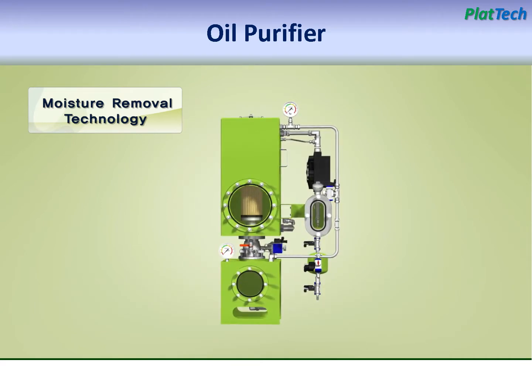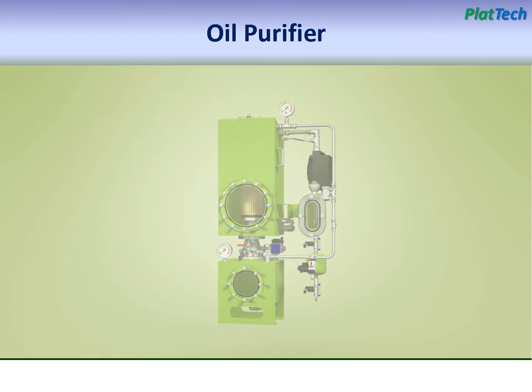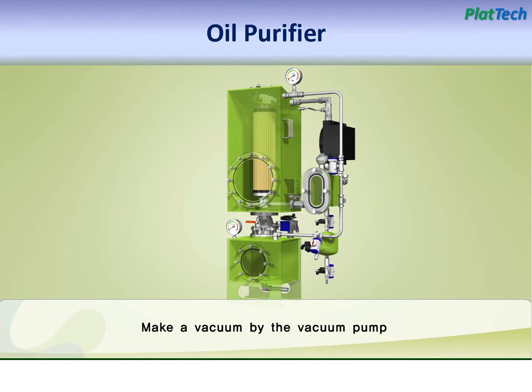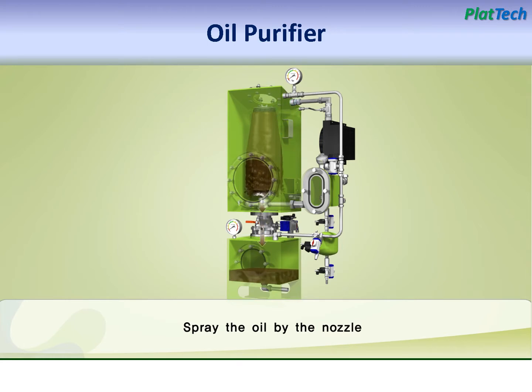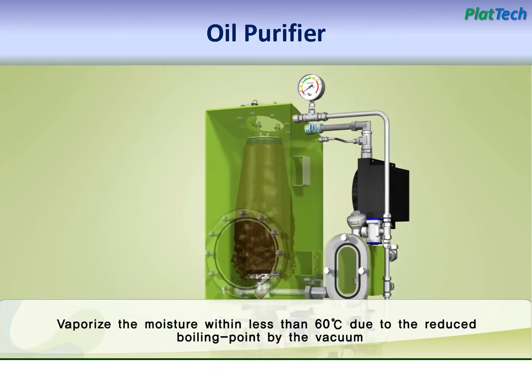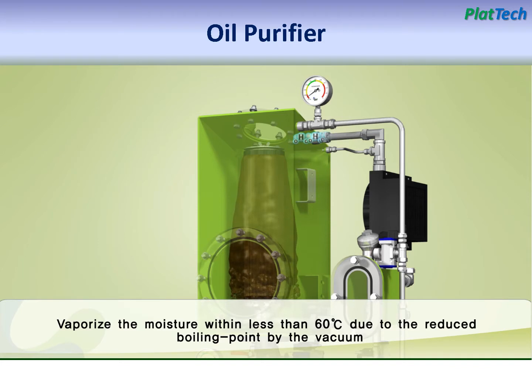For water removal section, pure vacuum distillation technology is used to remove dissolved water and gases more effectively. Vacuum pump will control high system vacuum and oils are sprayed through the nozzle. High vacuum will allow water to be evaporated below 60 degrees Celsius while oils are still under their bubble point, so oil loss by entrainment can be minimized. We will explain about each part of the system more in detail.